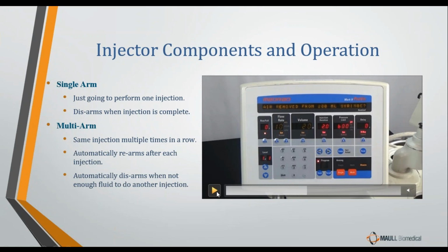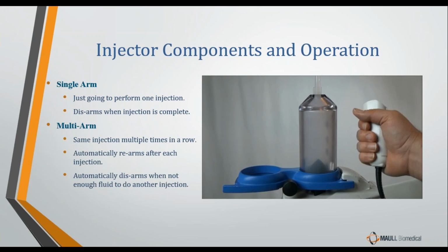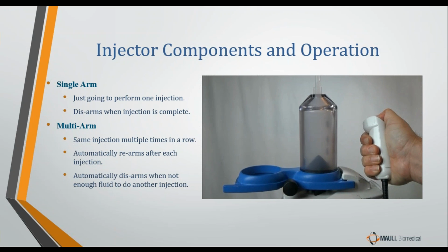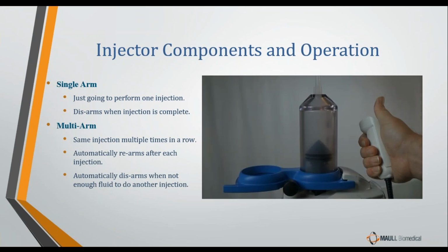Now, if the operator knows they're going to do the same injection over and over again, all right, we're going to shoot the same 10 milliliter per second flow rate and same 20 milliliter volume for multiple shots in a row, so I don't have to rearm after every single shot. We can hit multi-arm, which is what we just did. When we perform our injection, we hit the button, the injection's over, and without rearming, you just hit the button again, and it will shoot again. It will keep this up as long as there is enough fluid left in the syringe to give us the volume that we requested in the protocol. It will continuously rearm itself after each shot until there's not enough fluid to do another shot. So that's the difference between a single arm and a multi-arm injection.